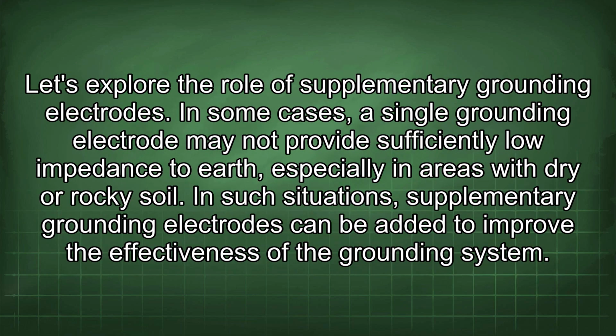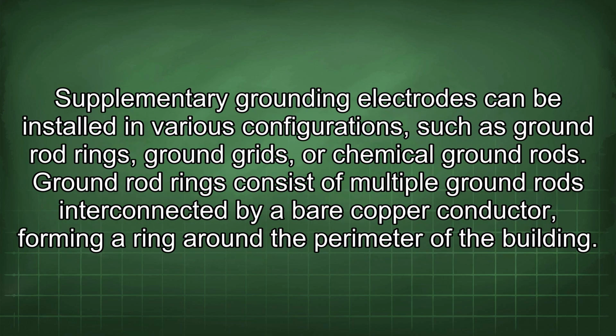Let's explore the role of supplementary grounding electrodes. In some cases, a single grounding electrode may not provide sufficiently low impedance to earth, especially in areas with dry or rocky soil. In such situations, supplementary grounding electrodes can be added to improve the effectiveness of the grounding system. Supplementary grounding electrodes can be installed in various configurations, such as ground rod rings, ground grids, or chemical ground rods.